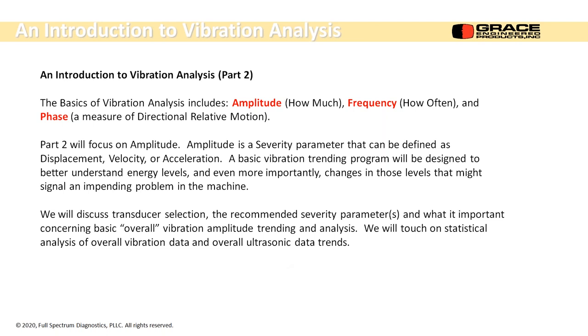This is a secondary trending mechanism that the GRACE transducers have to offer. The first is you're going to take an overall level, you're going to trend that. They also have spectrum and waveform capability on demand, but also they're putting in one of the transducers in the triaxial that is going to be a higher frequency transducer, and we can play with that, filter it, and adjust it so that we can see ultrasonic vibration. And that's very high frequencies, and it's an early indication of bearing failure. So I think next time I might mix it up a little bit and show you some ultrasonic trends and some technologies out there that might be of benefit for the GRACE product.